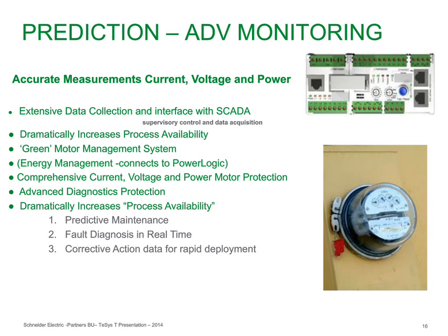So it basically gives you information to keep you up and running, which is incredibly important for any process that you have. As well, a lot of people will have software updates on equipment, but when it comes to firmware, they oftentimes have to replace devices. One of the beauties of TeSys T is we have both software and firmware updates available through the programming of the unit. So in this case, we don't need to replace devices. If we have firmware updates, we can do them through programming into the unit as well.